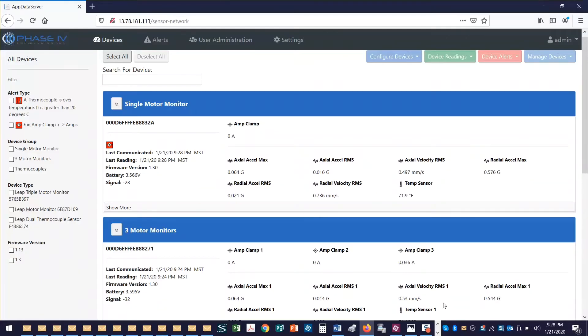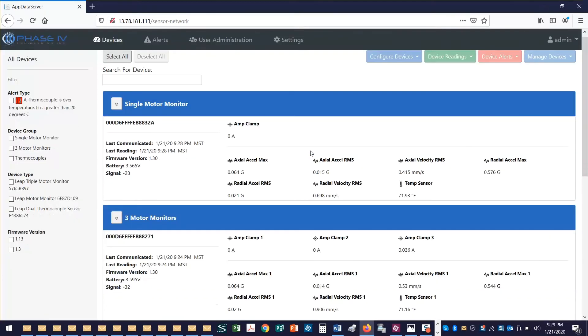Wireless sensors have also gone beyond the hype of edge computing to truly leverage on-sensor edge computing. Some sensors, like vibration sensors, require fast sample rates and collecting thousands of data points. By crunching the data and doing sophisticated analytics at the sensor, 20,000 data points taken at 5 kHz can be reduced to six key standard actionable metrics and transmitted over the air in just a few milliseconds.